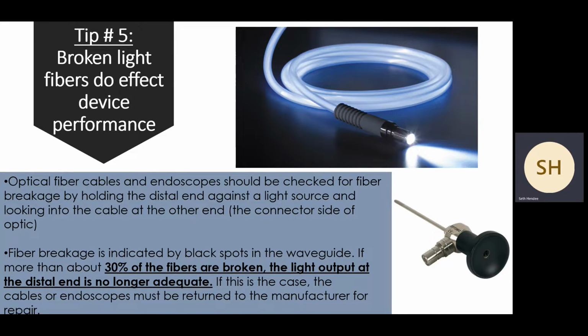We have it on our table, we hold one end up to the light, or we hook a device to it that can push light through, and we visualize the other end. So amongst the things that we have to test and that we have to look for, this is a very simple procedure. Here's the hard part. Fiber breakage is indicated by black spots. If you get more than 30% of the fibers broken, the light output at the distal end is no longer adequate.